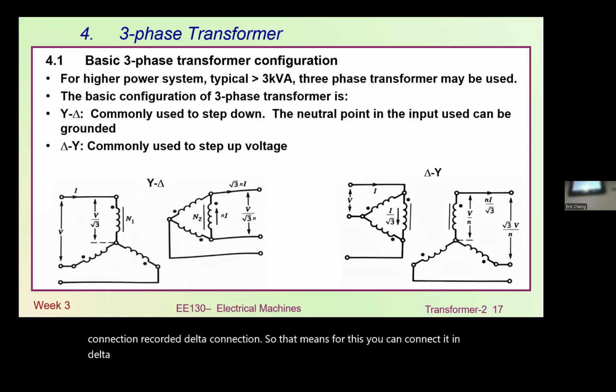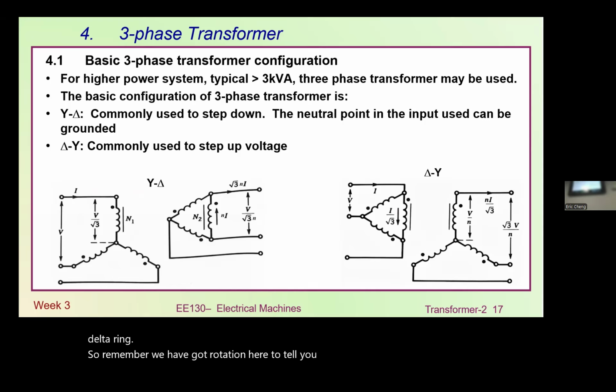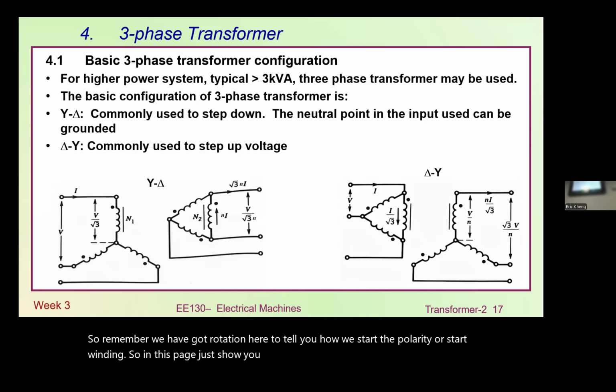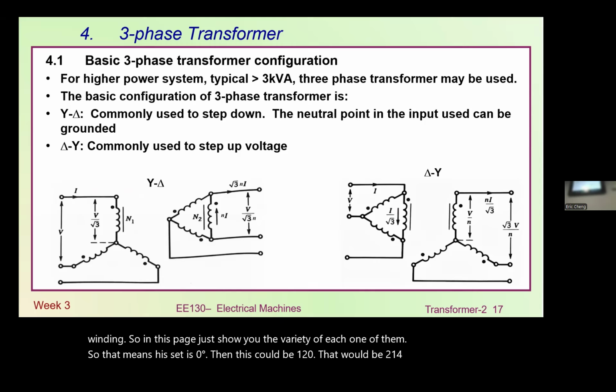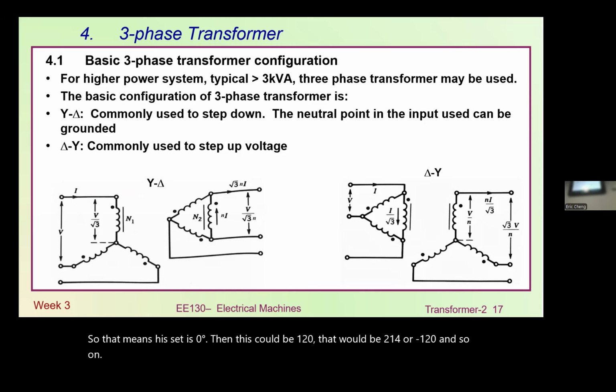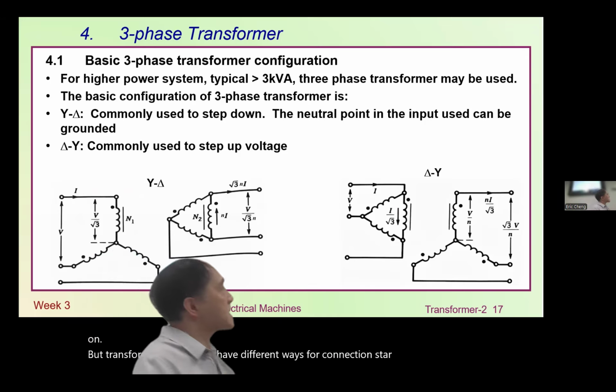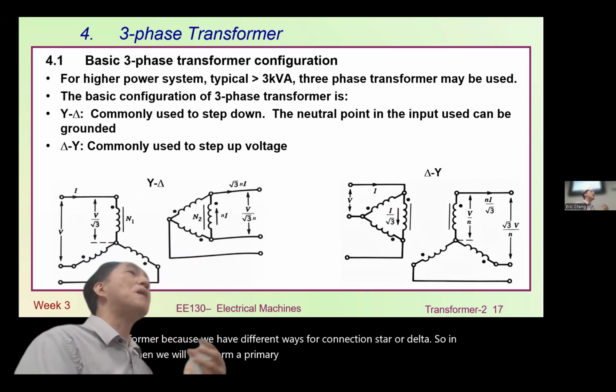We have dot locations here to show the polarity, or how we start the winding, for each one. So if that is 0 degrees, then this will be 120, and that will be 240, or minus 120, and so on. Because a transformer can be connected in star or delta, on the primary side and the secondary side, we can connect either side in delta or star independently.